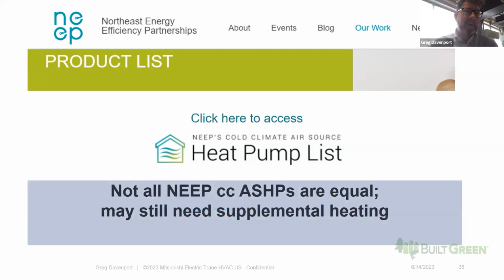A couple things about the NEEP cold climate heat pump list: it covers a wide range of products. This is approximate, not precise, but minimum heat output at probably 17 degrees needs to be about 75%. That's not a very high bar to hit for cold climate heat pump performance. So I don't want any builder or HVAC contractor to think that just because a heat pump is on that NEEP list, they'll get 100% of the heat at their design temp. You still have to be careful. You have to do proper heating and cooling load calcs, then proper manual S selection to derate for whatever your design temp is. I'm a little concerned that could be tricky for people, but this is a great list, a really good step forward, and a great place for us to start.